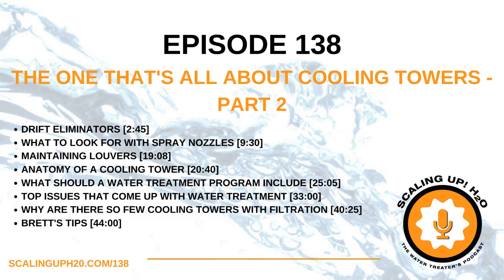It sounds like the first thing is you go have that discussion with them. We know the percentage of plant personnel that actually read the reports is very low, but you still need that paper trail. So have that discussion. Say, I've talked to the manufacturer, I've talked to the sales rep who sold this equipment, and he talked to the manufacturer, and they confirmed we're operating outside of OEM specs. This is a concern, here's what I'm seeing, and here's what will happen. Whether it's a scaling concern or a corrosion concern, I think it's good to tell them what they're doing wrong, but you have to reinforce it with: if you keep doing it this way, this is the outcome. And then put it in writing.